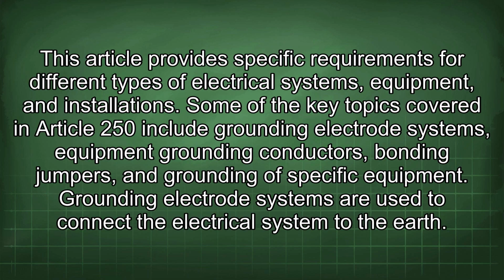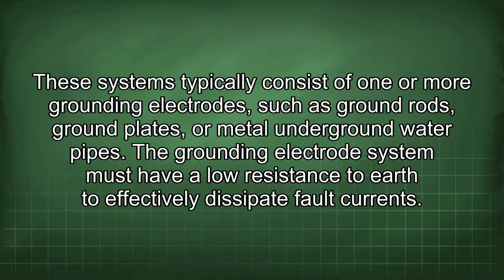This article provides specific requirements for different types of electrical systems, equipment, and installations. Some of the key topics covered in Article 250 include grounding electrode systems, equipment grounding conductors, bonding jumpers, and grounding of specific equipment. Grounding electrode systems are used to connect the electrical system to the earth. These systems typically consist of one or more grounding electrodes, such as ground rods, ground plates, or metal underground water pipes. The grounding electrode system must have a low resistance to earth to effectively dissipate fault currents.